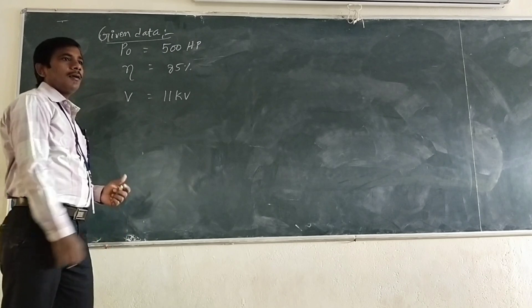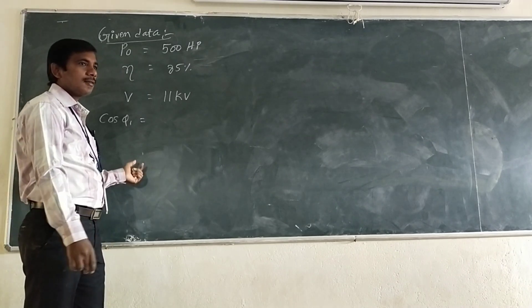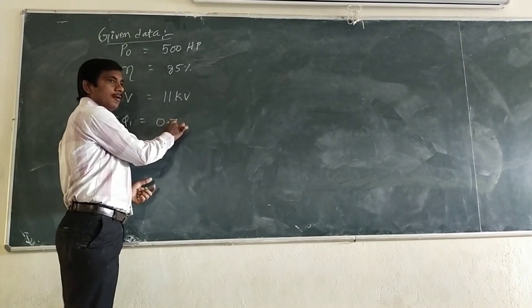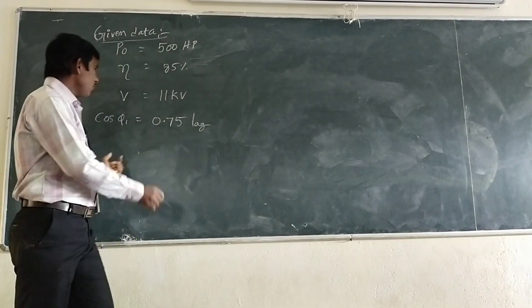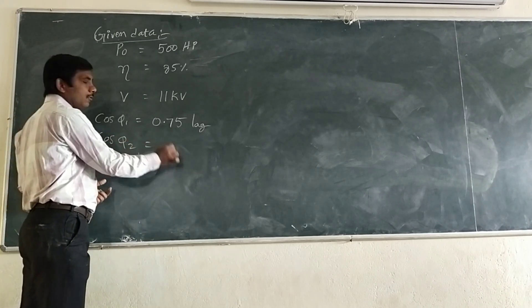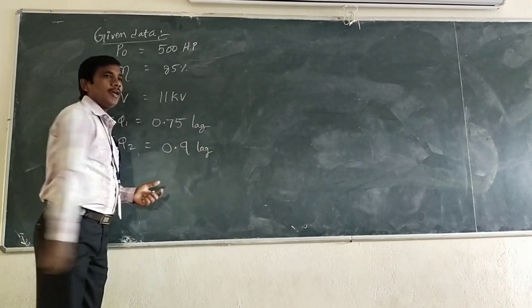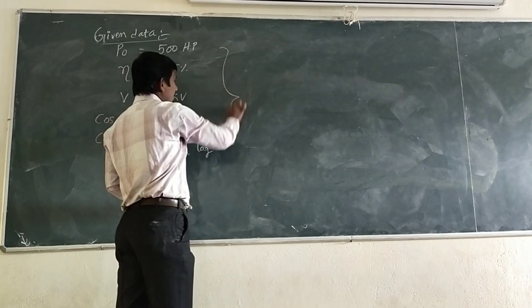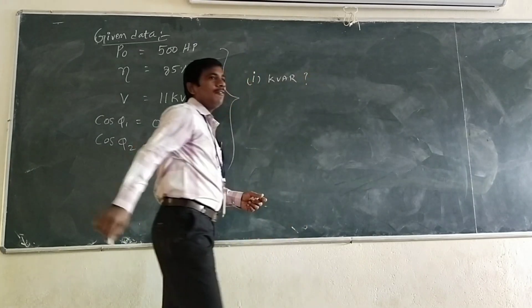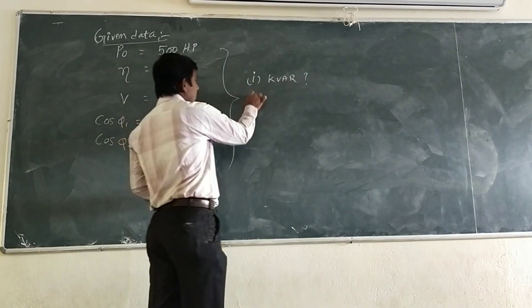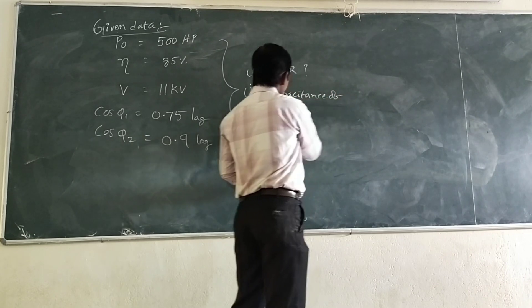The supply voltage is 11 kV. Initially, what is the power factor? The initial power factor, cosφ₁, is 0.75. We have to improve the power factor to cosφ₂ equal to 0.9. We have to connect capacitors in star as well as delta. The second item to find is the capacitance of each unit — in star and delta.